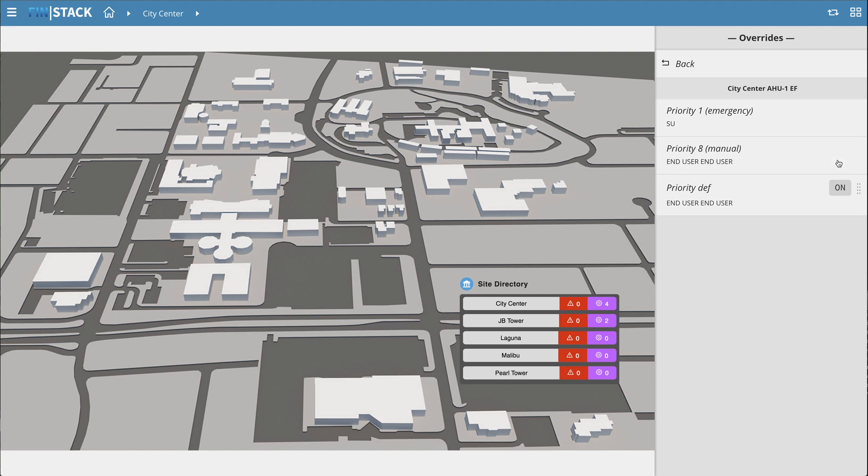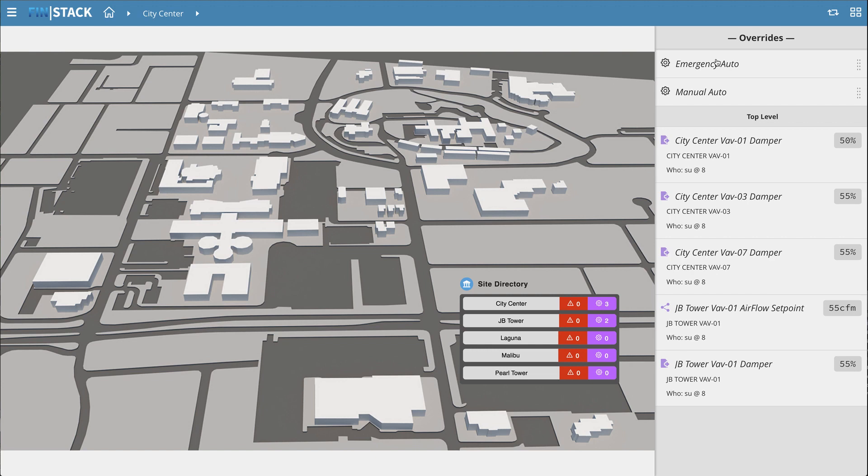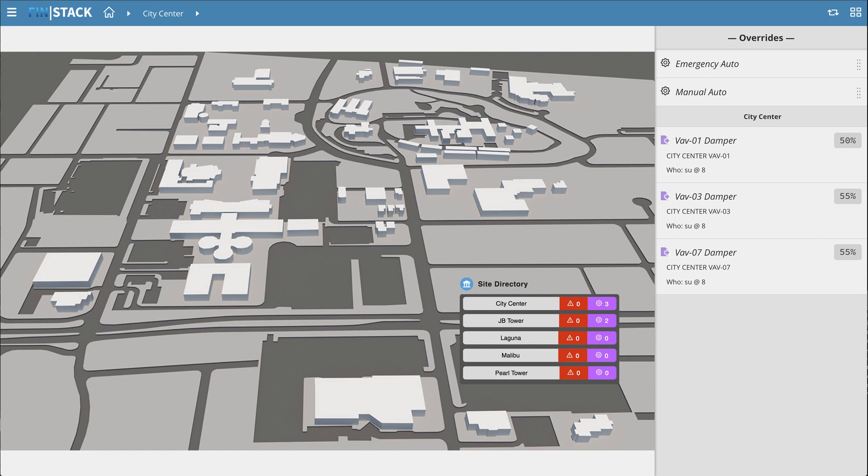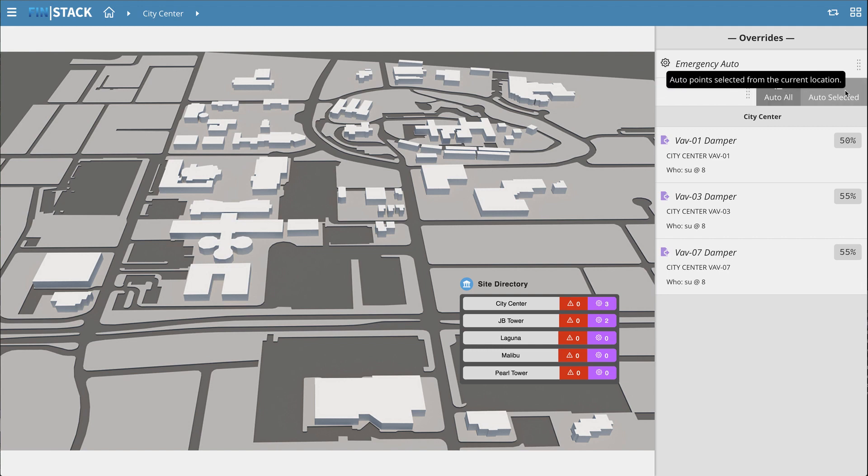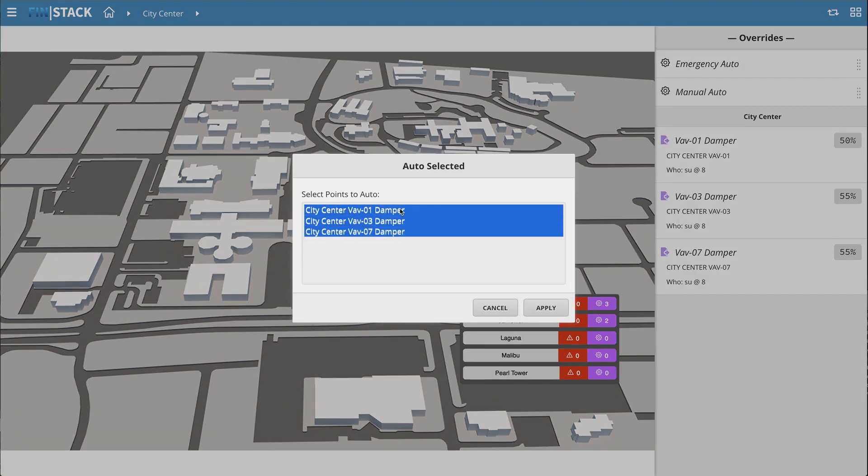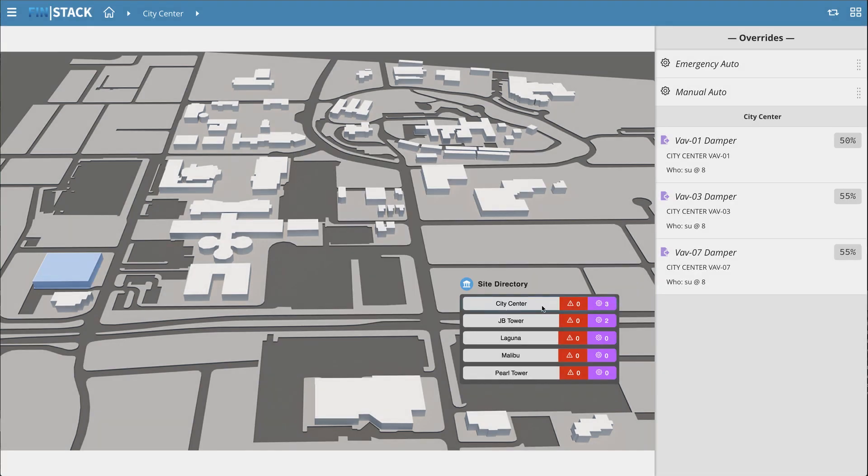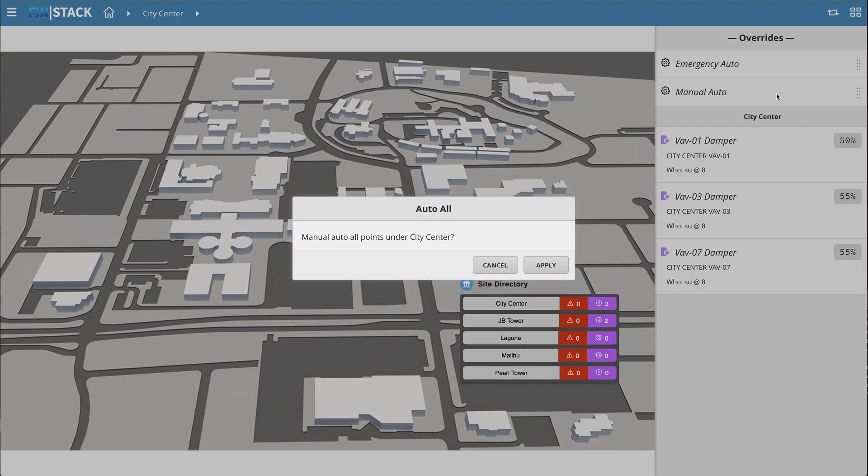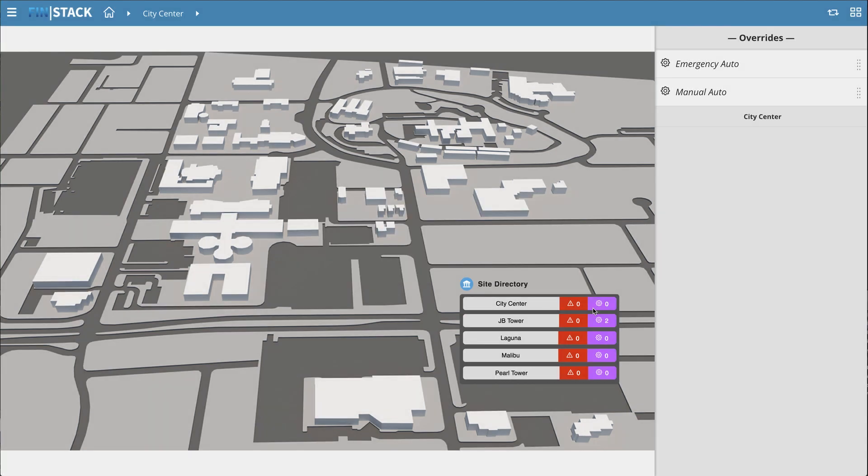If you go back a step, you also have the option to do Batch Autos by clicking on the Emergency or Manual Auto Options on the top. The Auto Selected option allows you to select which points you want to auto out. The Auto All automatically autos every override under your current context.